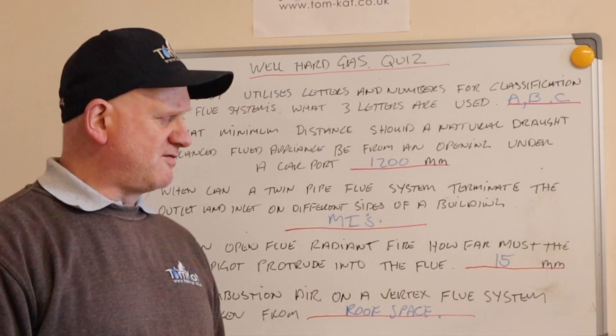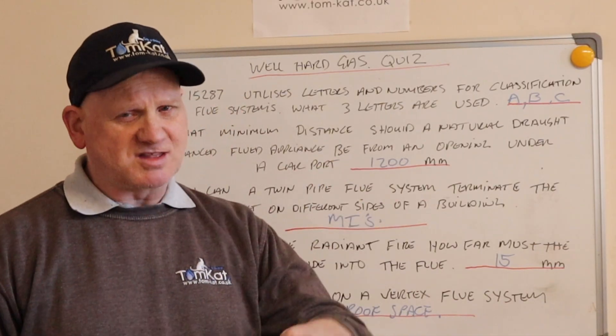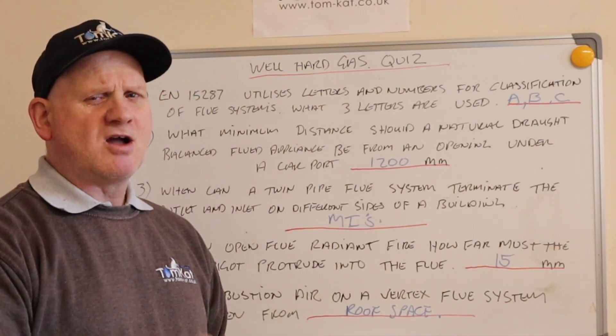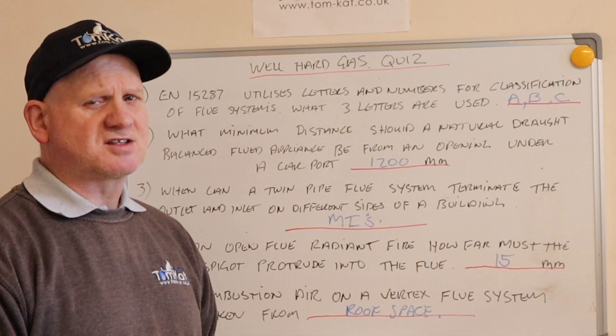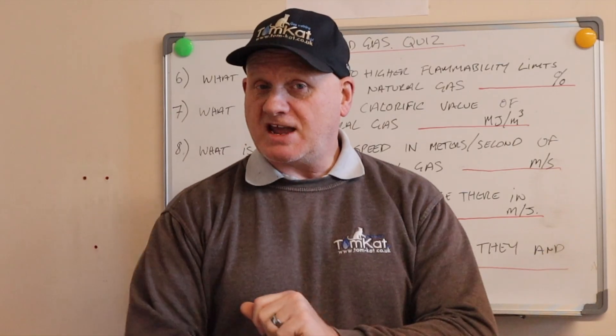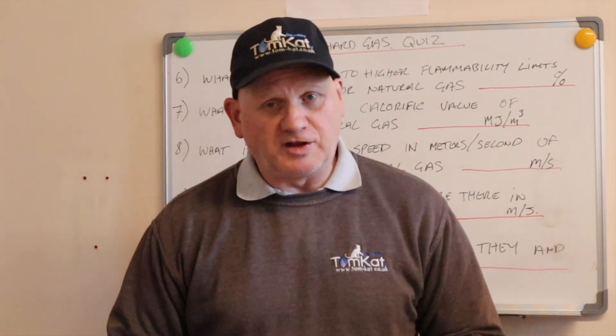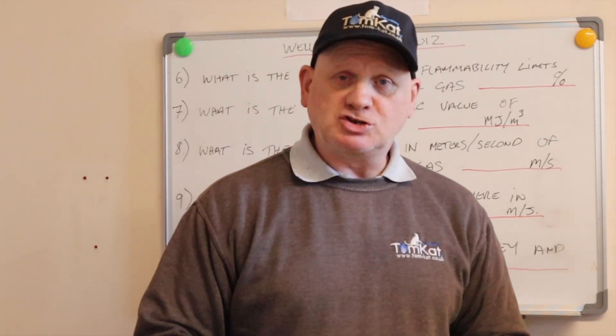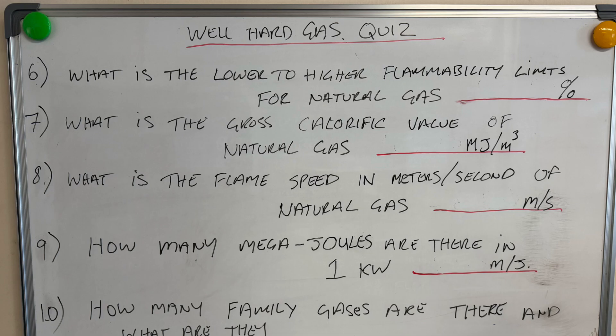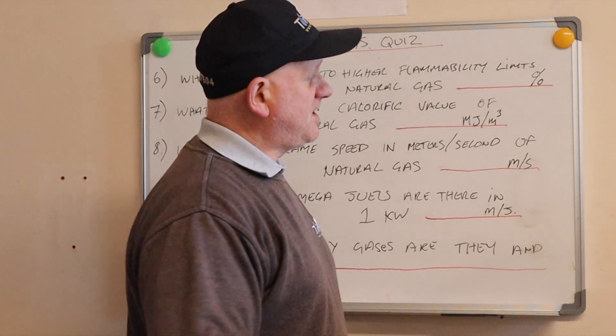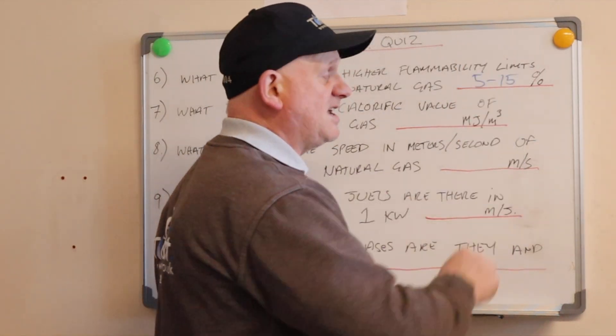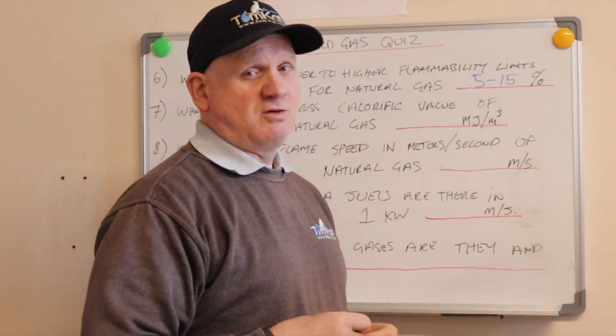How are you doing so far on the first five? Let me know in the comments below. Now for the next five questions, which are mainly on the properties of natural gas. Question number six: what is the lower to higher flammability limits for natural gas in percentage? Hopefully you said 5 to 15% gas in air.